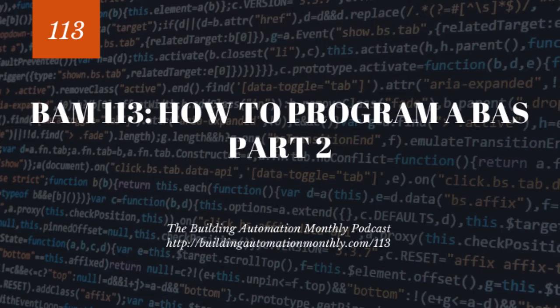You have now highlighted everything you're supposed to program. Now you need to go and order and number these. So for example, in the YouTube video, I go through a rooftop sequence of operations and I challenge the viewer and I say, hey, when you turn on the rooftop, what is the first thing you should have happen? And a lot of folks will say, turn on the fan. And that's absolutely wrong. It's open the dampers.